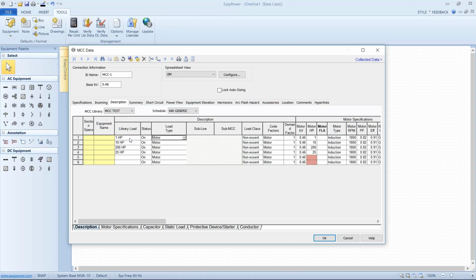Now, whether I'm using library load or not, the designations here can be changed. And as I mentioned earlier, we can designate a motor, a load, a VFD, sub-panels or sub-MCCs, and then we can designate loads with time current characteristic curves. For the purpose of coordination, I want to have a time current characteristic curve for that particular load. So in this case, I would designate the motor with a TCC, and I could do the same thing for a VFD, and I can also group large loads or large numbers of motors with commonality on sizes. So let's go ahead and finish a couple of these, and I'll show what the results are.